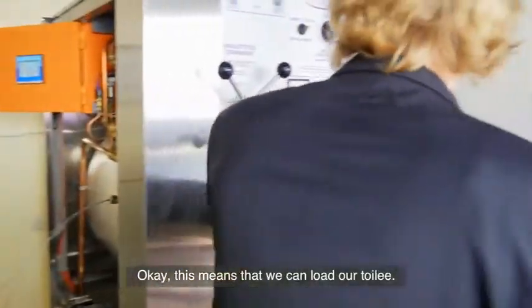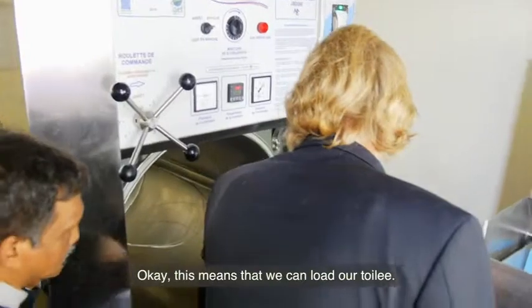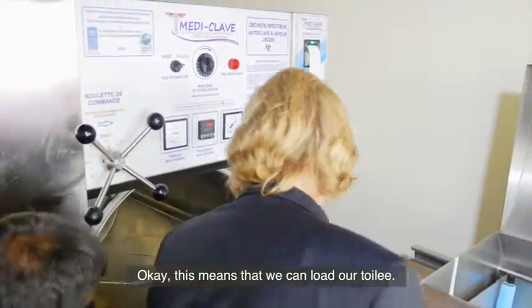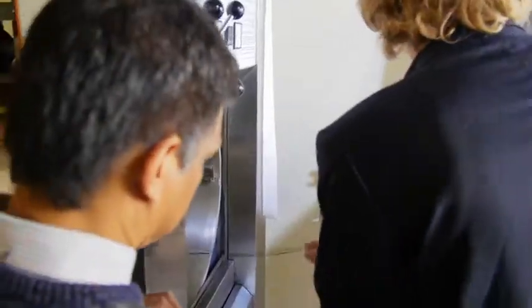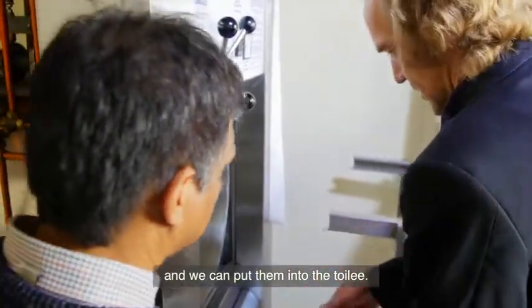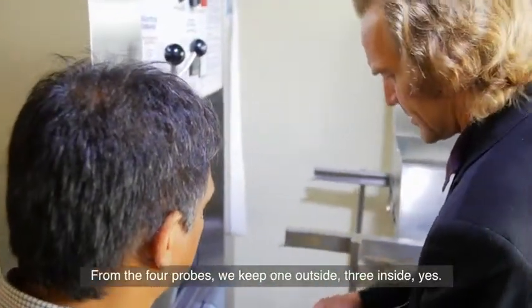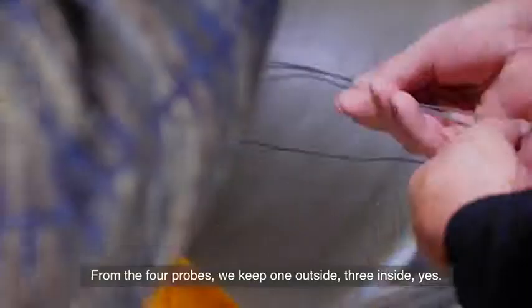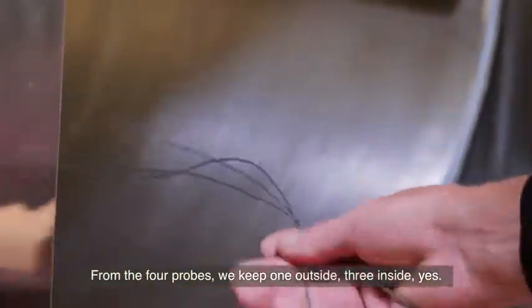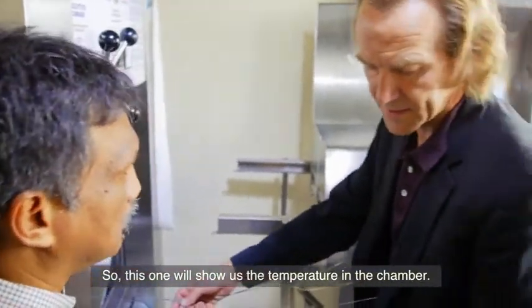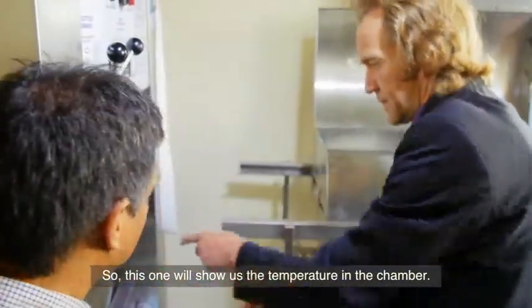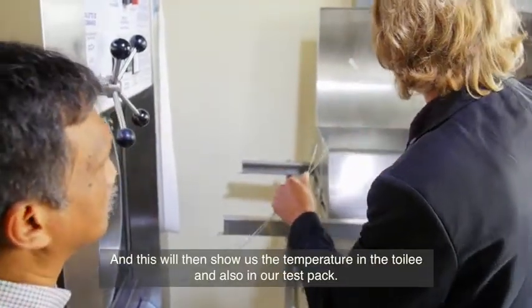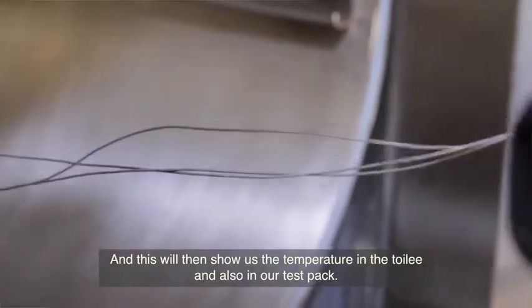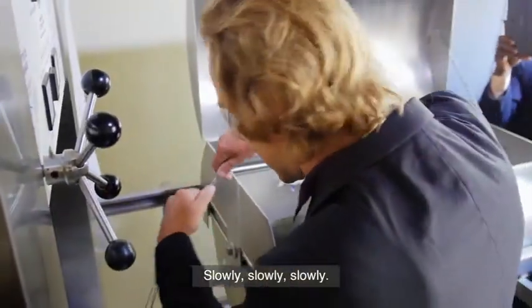Okay, this means that we can load our trolley. As said here, the probes are hot. Get them out, and we can put them into the trolley. From the 4 probes, we keep 1 outside, 3 inside. So this one will show us the temperature in the chamber, and this one will then show us the temperature in the trolley and also in our test pack. Slowly, slowly, slowly.